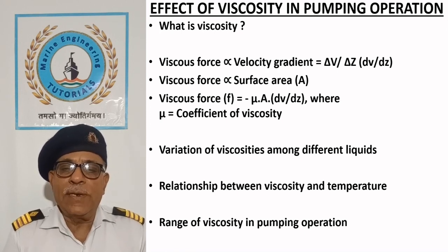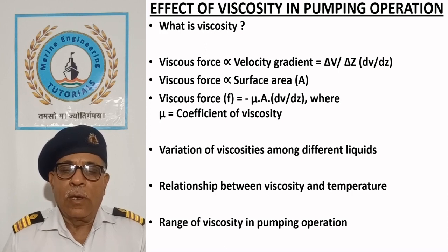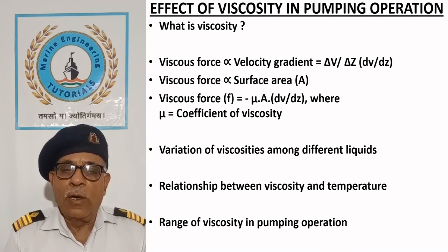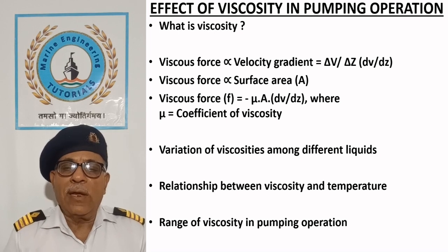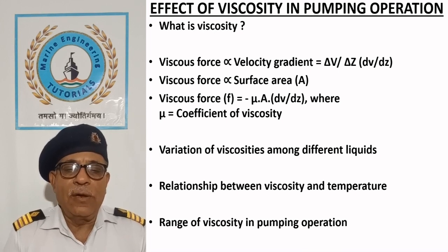Range of viscosity in pumping operations: Selection of a pump is mainly based on head and flow requirement of the liquids, although viscosity is yet another important parameter. Centrifugal pumps are used for high discharge rate at low to moderate heads, and are used for low viscosity range between 0.1 to 200 cSt. A centrifugal pump cannot handle high viscosity liquids and is unable to create high vacuum at the suction compared to positive displacement pumps. While handling viscous fluids, load on the prime mover increases due to excessive shear force between fluid layers, and flow rate is greatly reduced. A heavy impeller is also required to withstand the additional force.